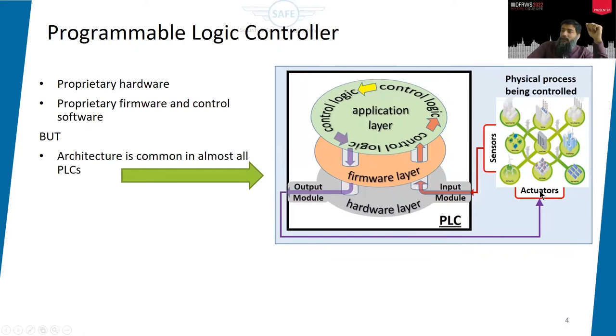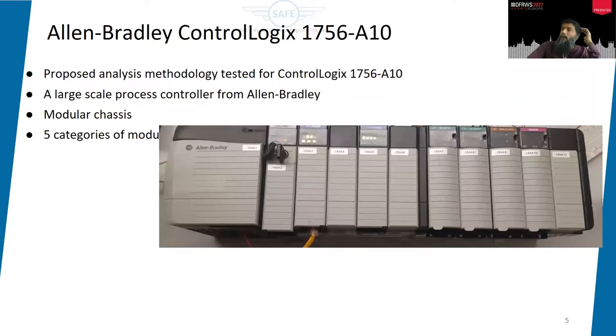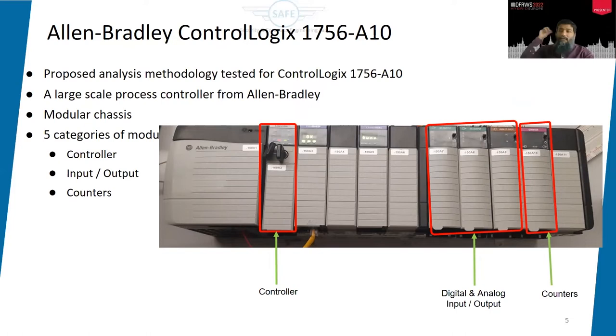In our case we have ControlLogix 1756. It's a modular chassis with a controller — the brain of the chassis — and different varieties of digital and analog input/output modules, dedicated counters because timing is very important in PLCs, communication modules like Ethernet, and the power supply unit.